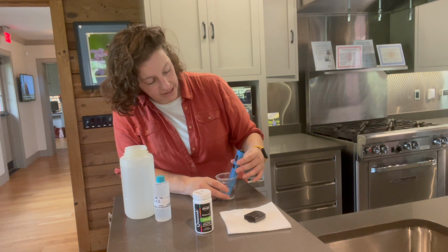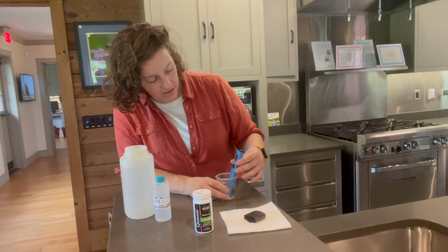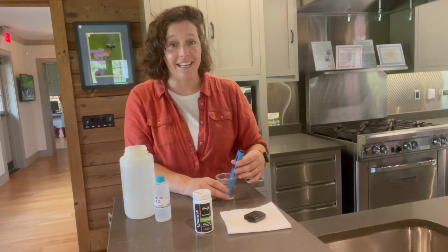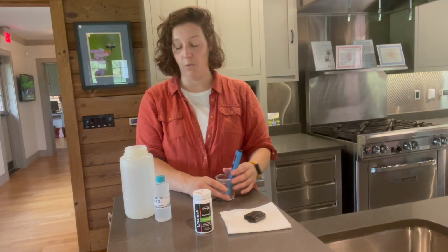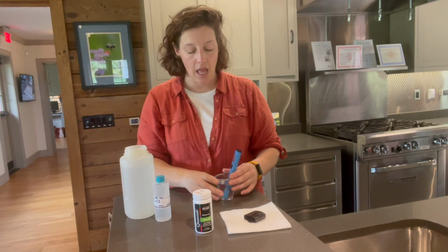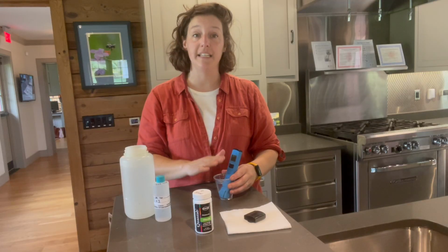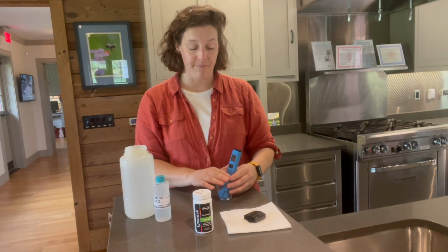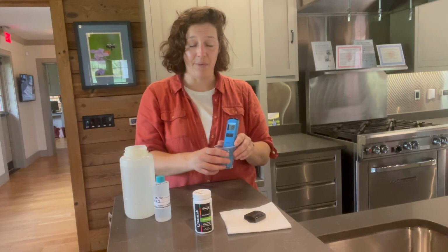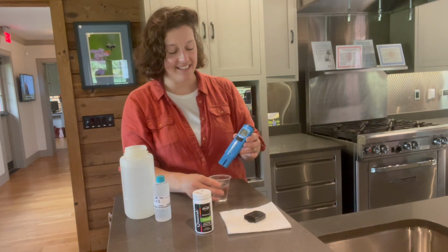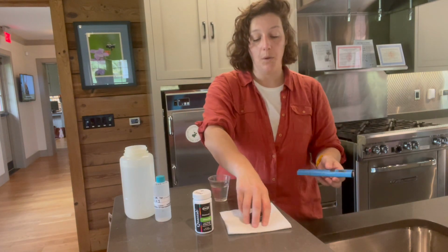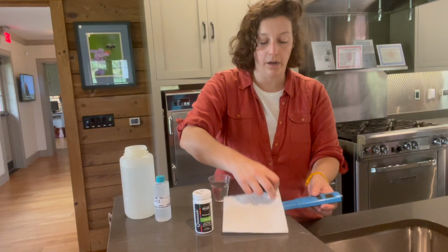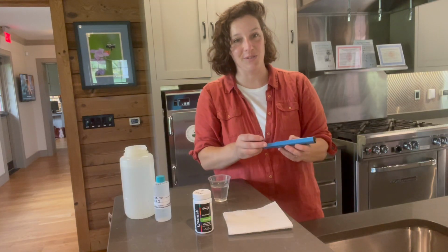All right, and it looks like our conductivity reading is 194 microsiemens per centimeter. So when you take your reading, you'll want to log it on a data sheet that has the site ID, the date, and the time of collection. So now that we have our conductivity reading, it's fast and painless. We can take our meter out of the sample, turn it off, and then we'll rinse it with clean tap water and pat it dry to store it for the next time we're using it.